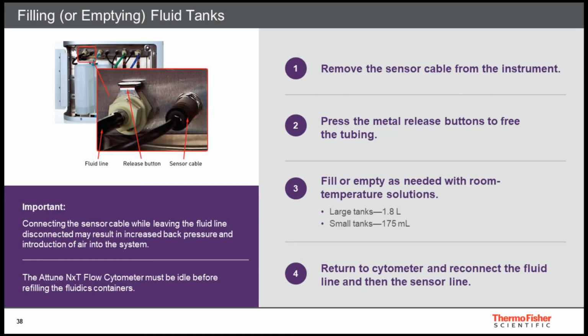When removing a container from the instrument, we recommend disconnecting the sensor cable first, followed by the tubing. To reconnect the container, plug the tubing first until an audible click is heard, and then connect the sensor cable. Improper connection of tubing may result in back pressure issues, and gone undiagnosed for a long period may harm the instrument.